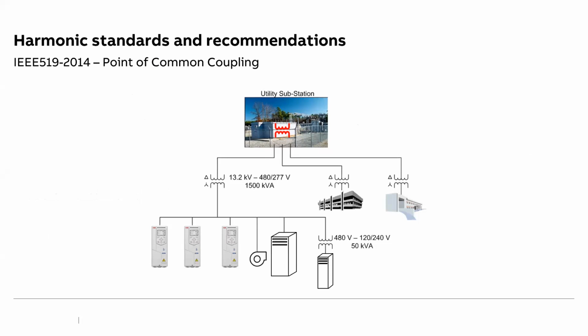For example, if there are multiple VFDs connected to a common feeder, and there are multiple such feeders, then each feeder can become a PCC. So we can design the filter or some mitigation technique at these various levels. Depending on the size, the overall harmonics and the mitigation level required, we can design the mitigation technique and the filter. Now we'll see what the different mitigation techniques are.